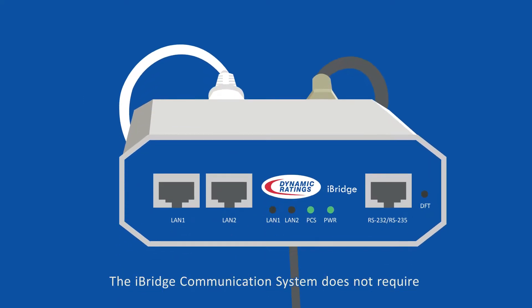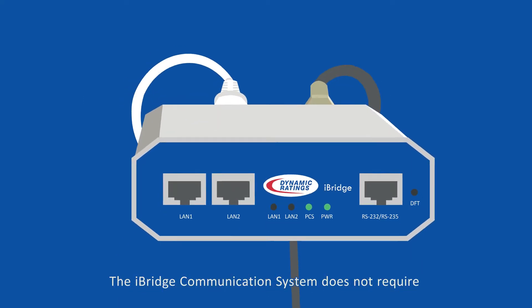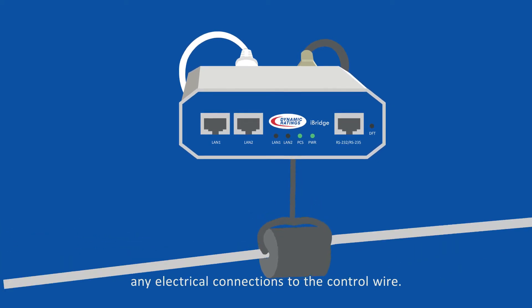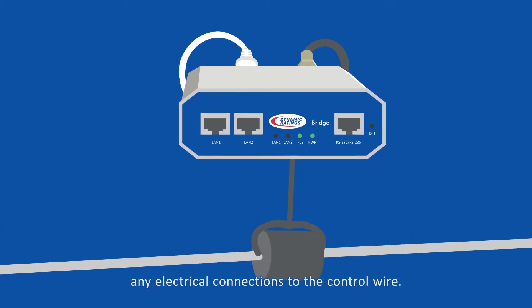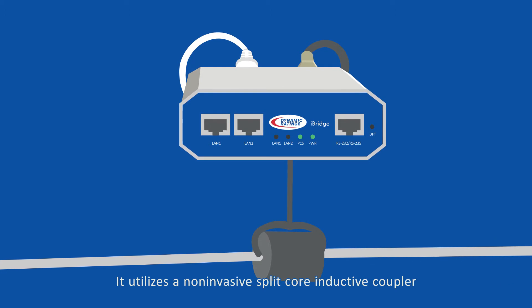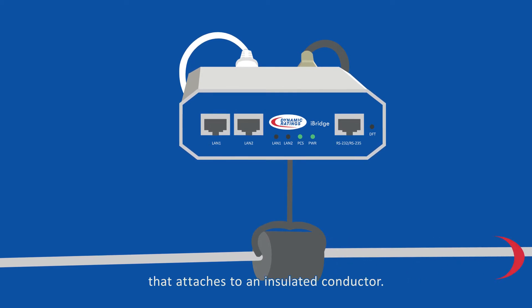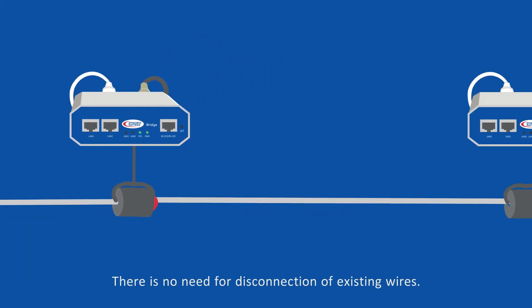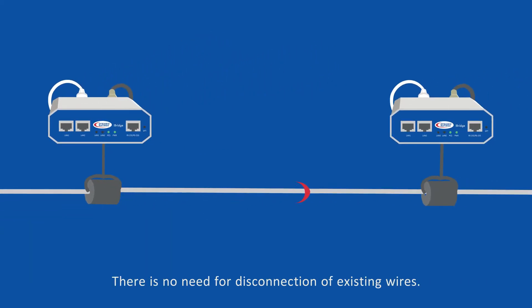Here is how it works. The iBridge communication system does not require any electrical connections to the control wire. It utilizes a non-invasive split-core inductive coupler that attaches to an insulated conductor. There is no need for disconnection of existing wires.